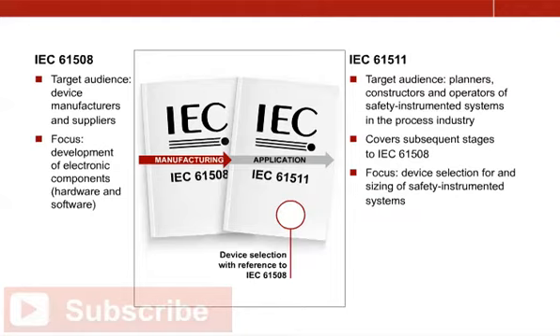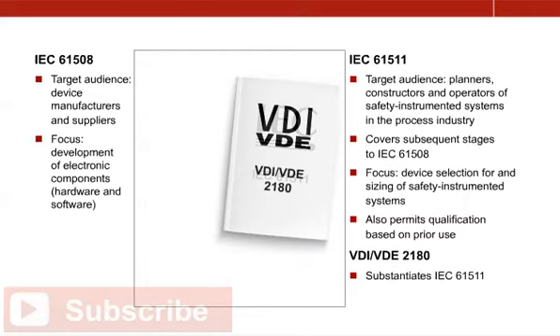If the standard cannot be applied to a component, or if it does not entirely cover the component's function, as is the case with mechanical components in field units for example, it is permitted according to IEC 61511 to provide evidence of suitability based on prior use and taking into account a quality management system implemented at the manufacturers.